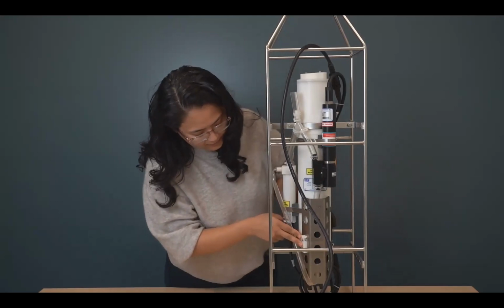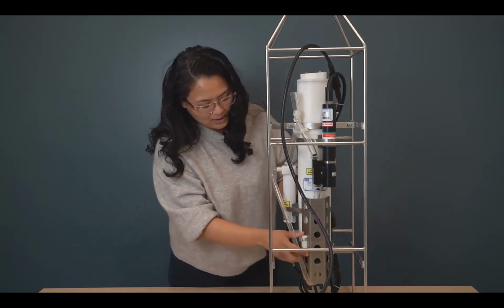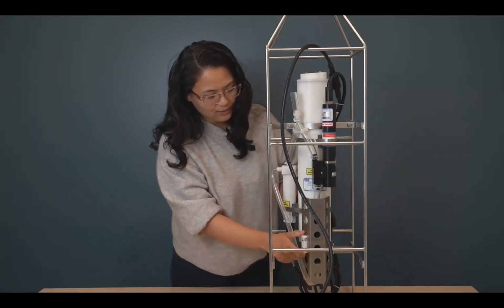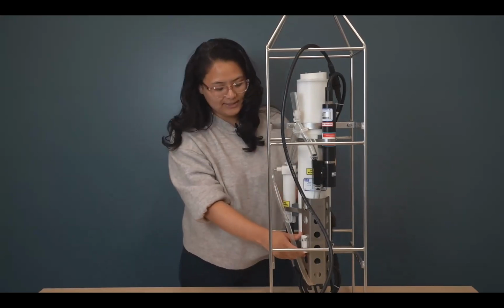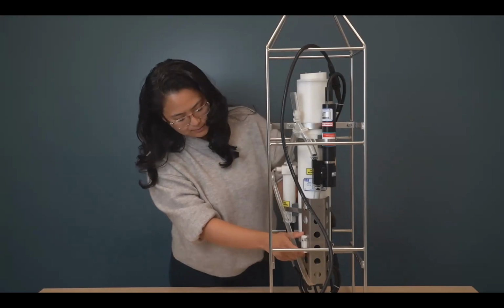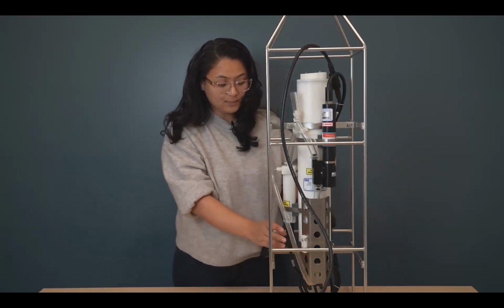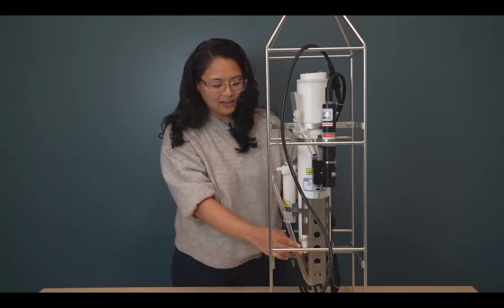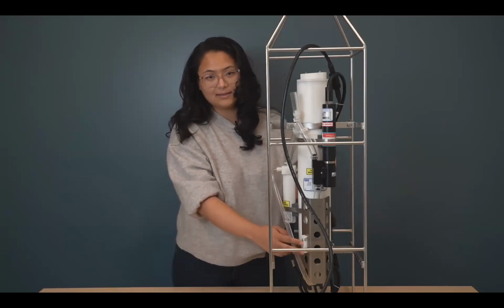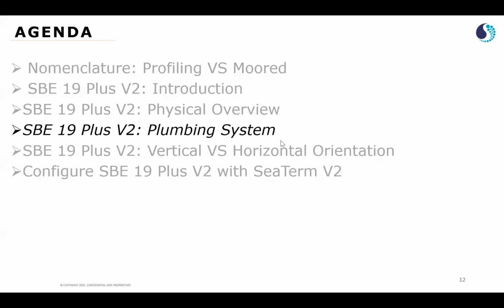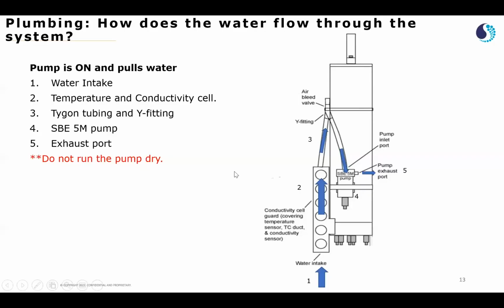Here I have what is called a magnetic switch, which is turned on or off depending on how you set up your SBE 19+ system. It is important to note that the magnetic switch only collects the data. And now let's see how the water flows into the SBE 19 system. It's important to make sure that the pump is on and it's pulling water and not pushing it.